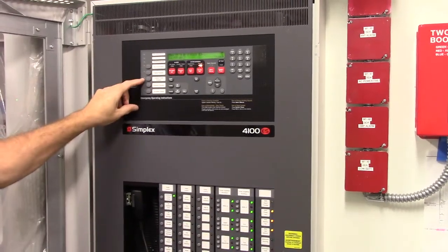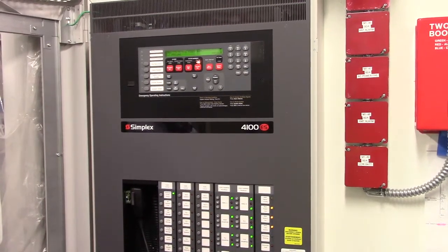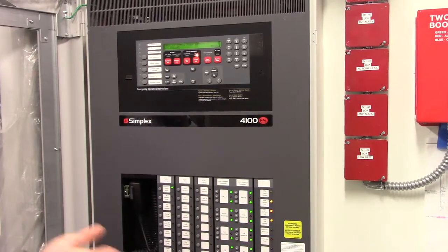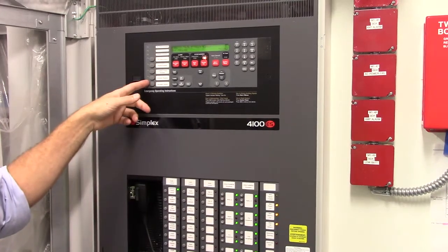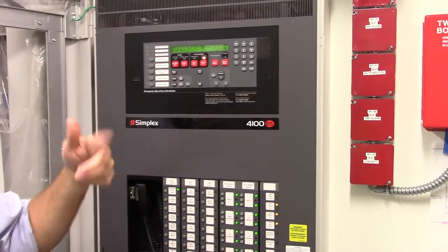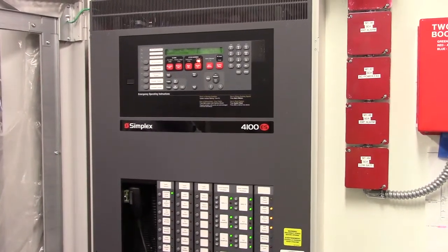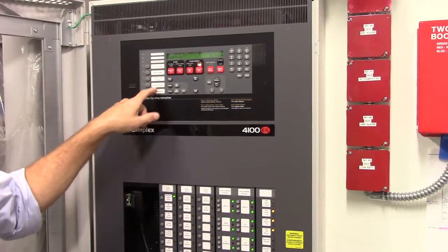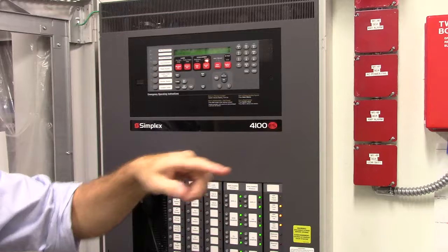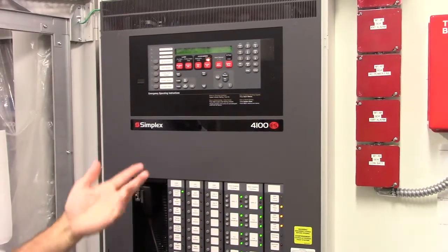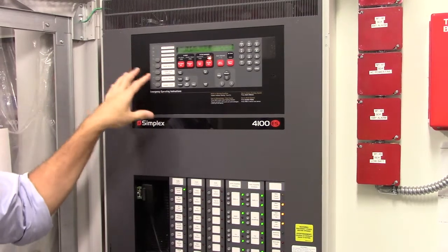Control point bypass will control any door holders, closers, interfaces to your card access system, HVAC shutdown, that kind of thing. Elevator bypass will stop it, so if you're doing any work around the elevator and they needed to test the smokes or anything, it'll stop the elevator from going into fire recall. Silent alert inhibit will stop the buzzer on this panel and the buzzers on the 3 panels in the remote command centers. If you guys are working or you get a trouble that's bouncing in and out, it won't stop any alarms from coming in or anything else, it'll just stop the buzzers.